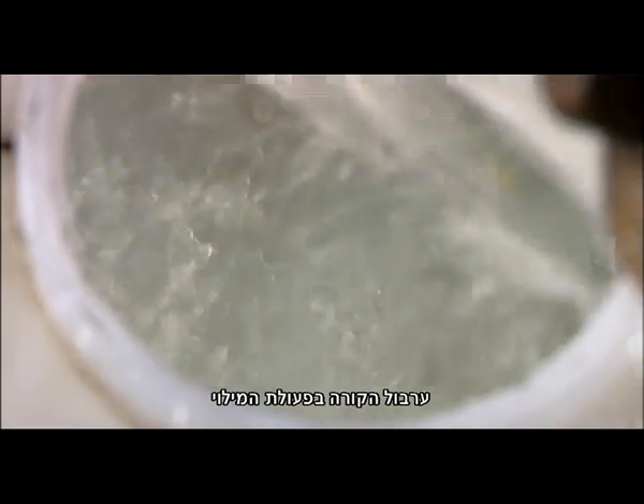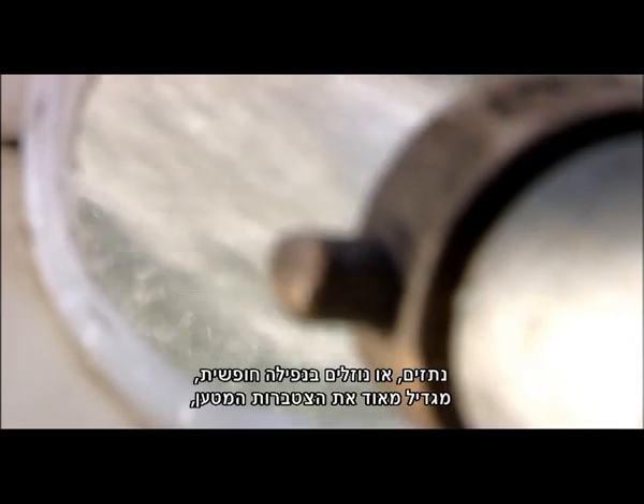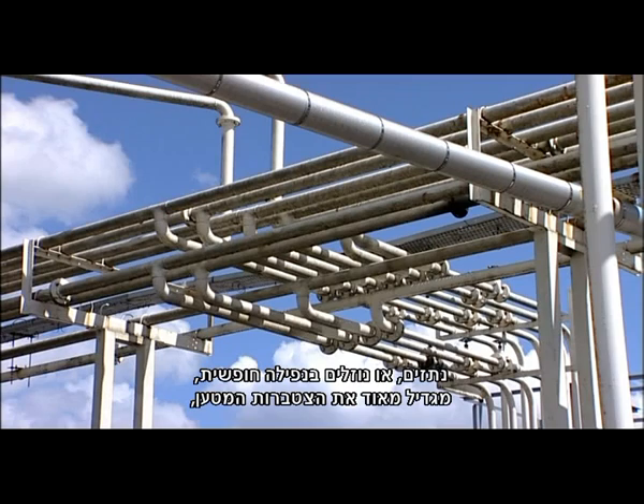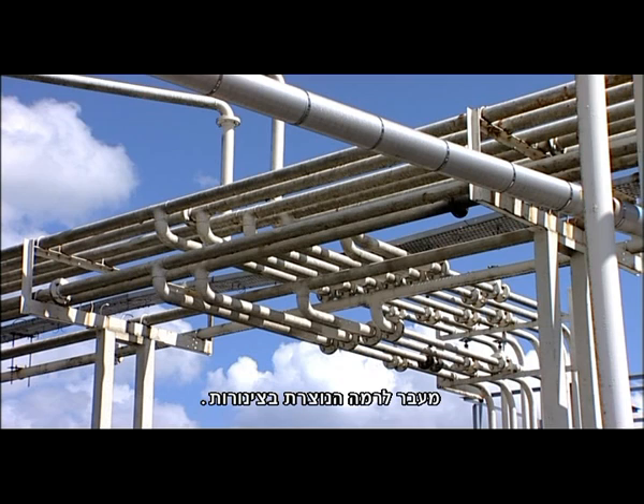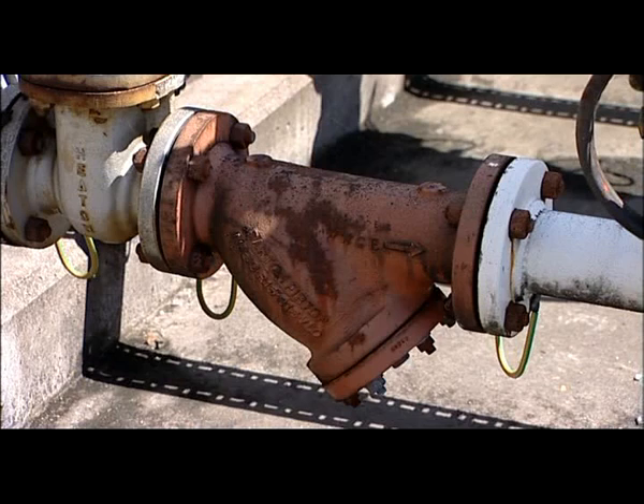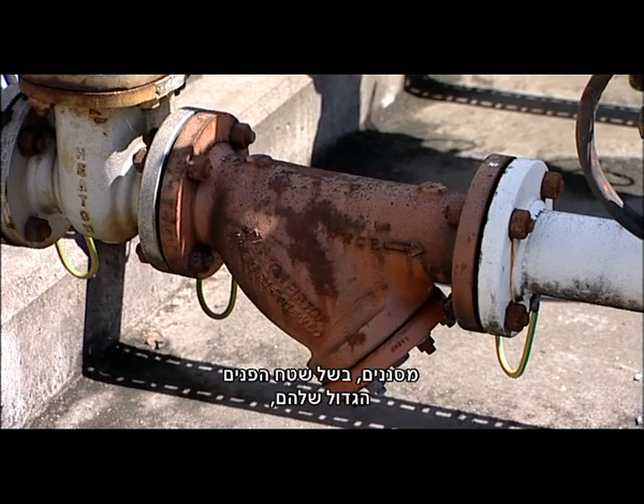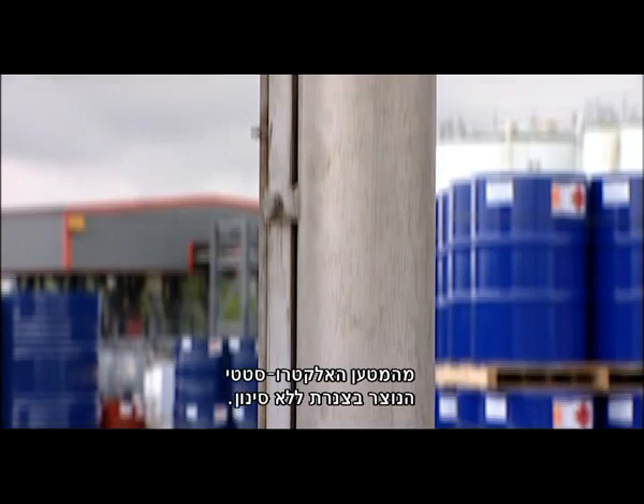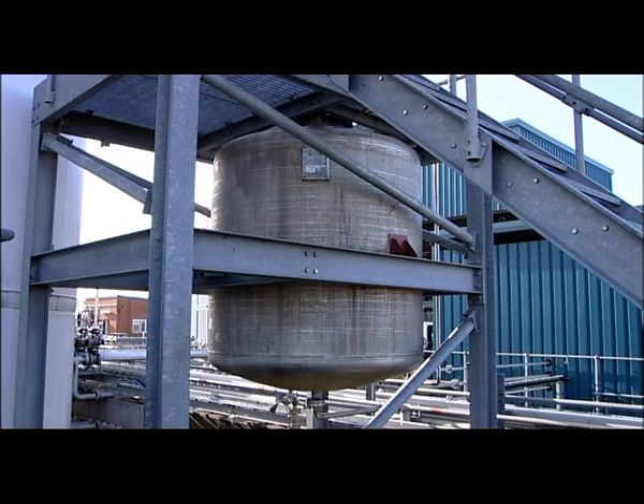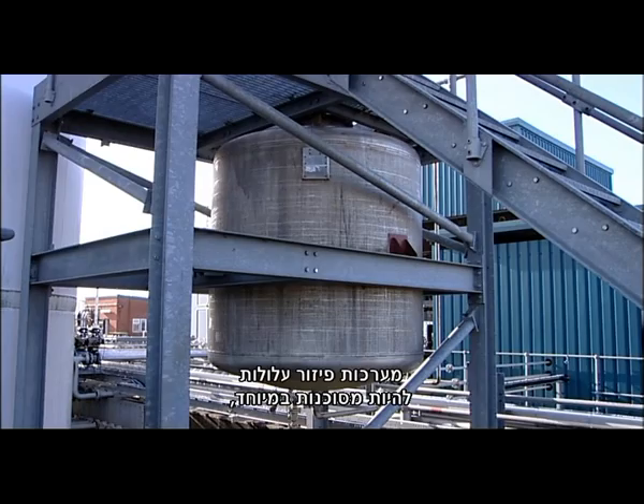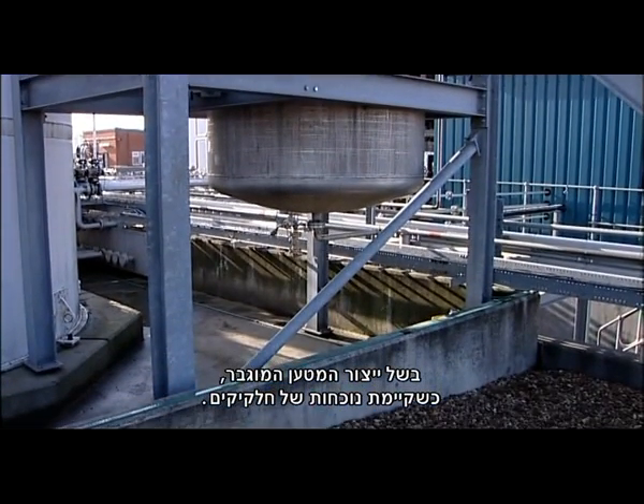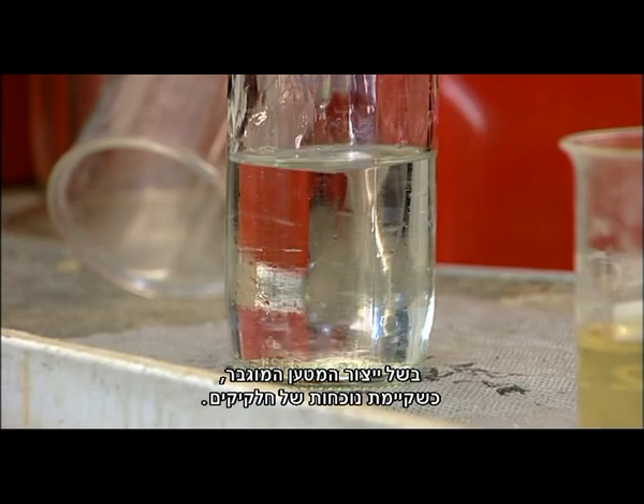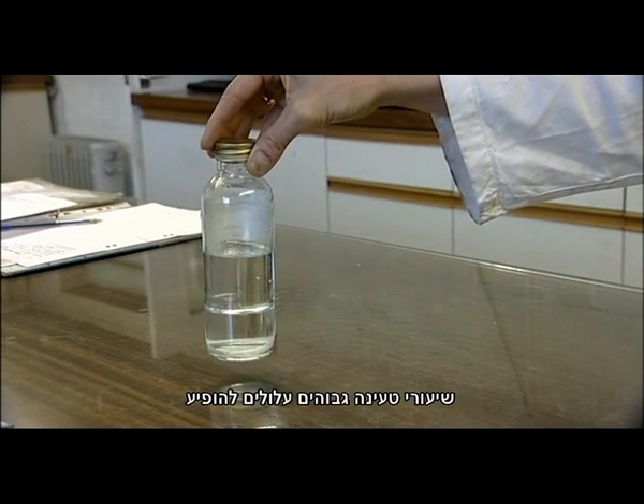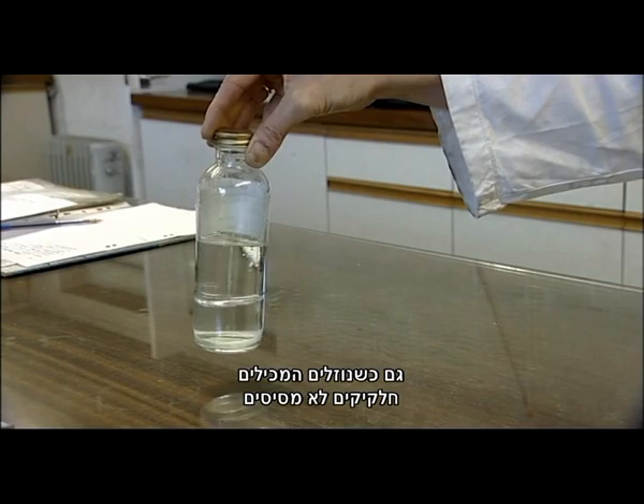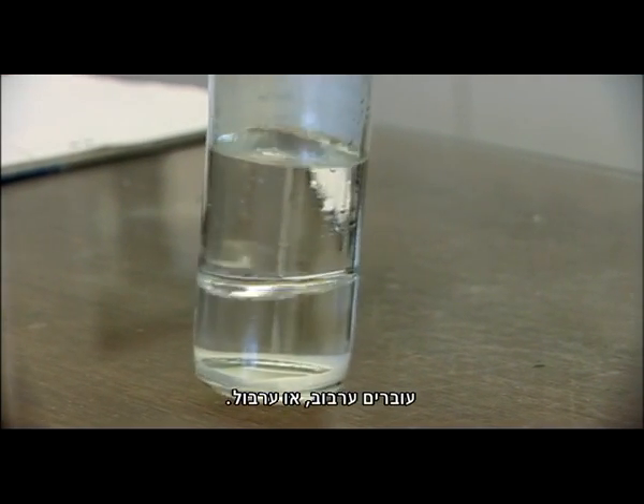Turbulence experienced in filling operations, caused by large flow rates, splashing, or free-falling liquids, greatly increases the charge accumulation beyond the level generated in pipes. Filters, because of their large surface area, can generate as much as 5,000 times the electrostatic charge generated in a pipe system without filtration. Dispersing operations can be particularly hazardous in view of the extremely high rate of charge generation when particulates are present. High charge rates can also occur when liquids containing non-miscible components are mixed or agitated.